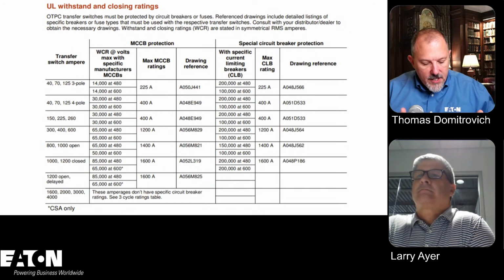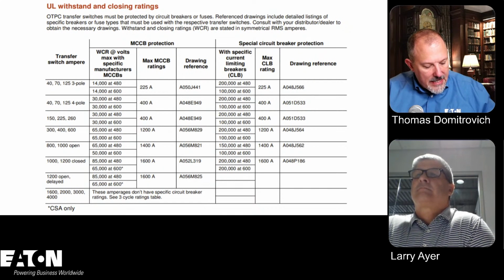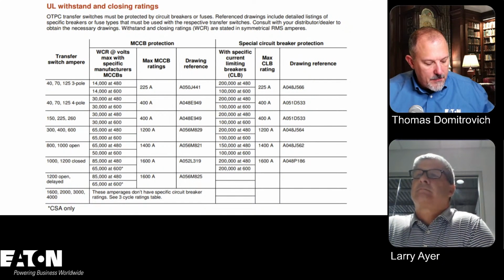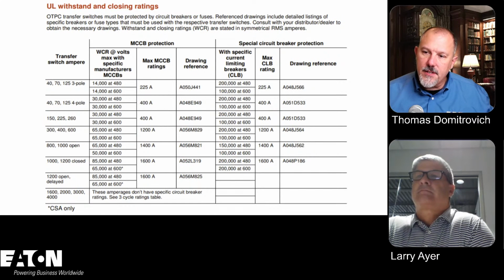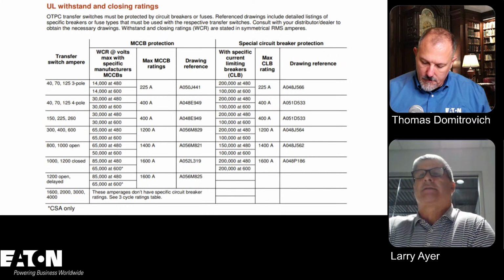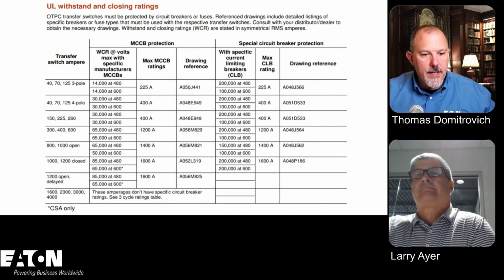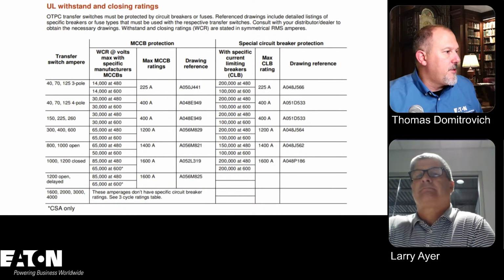But if I'm using it for my fire pump, I can't find anything in 695 that says it has to be listed like you would have for an Article 700 system. Yeah, and I do not see that either. That's an interesting point. Matt, that's a very good observation. I've got to look into that a little bit more.